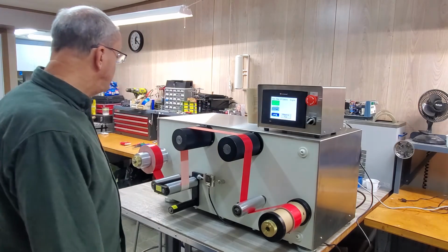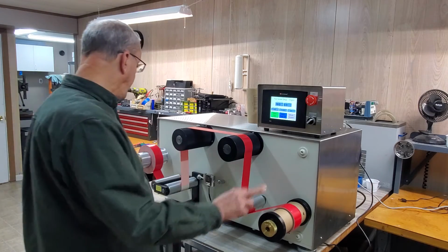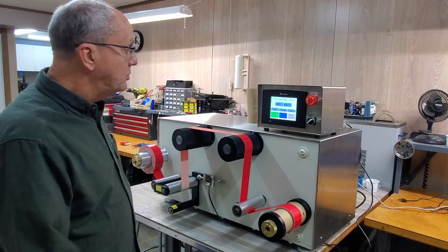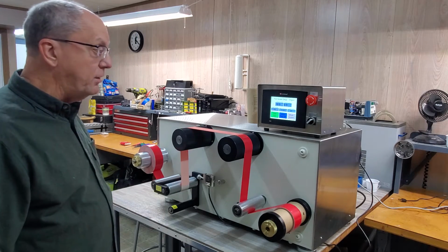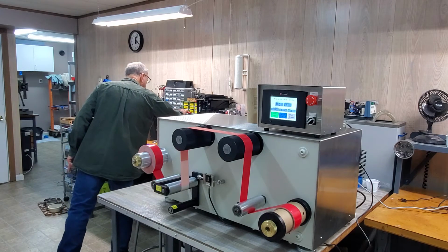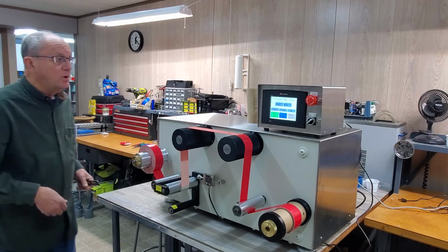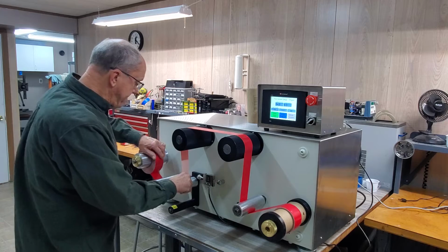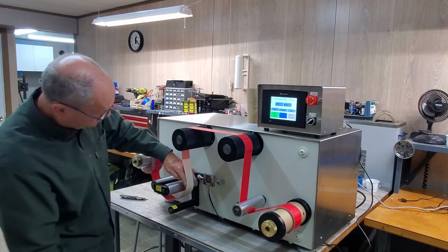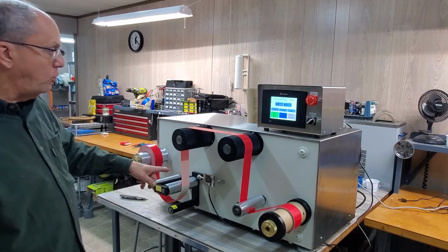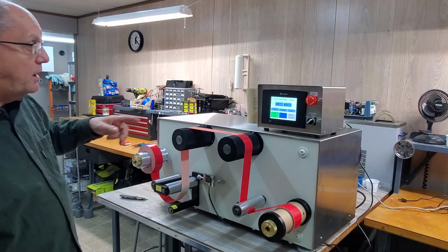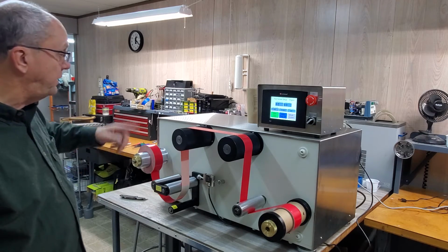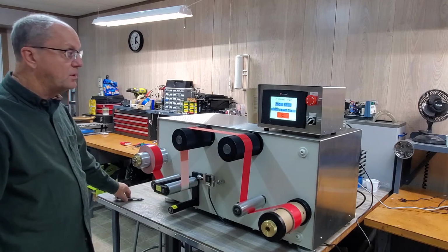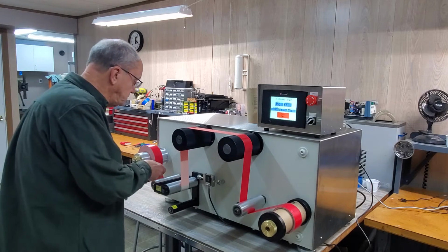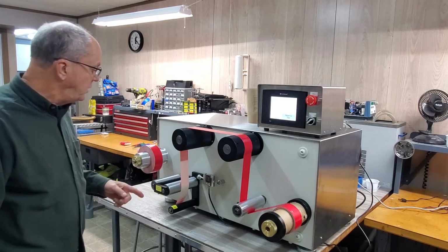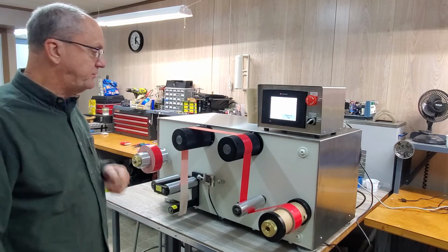Obviously, all this stuff can be changed at any time. So what I'm going to do is run a test, and I'm somehow going to make this thing go slack so that I can demonstrate how this auto shutoff works. So here we go. First of all, let's put some slack in the web. So you can see I have no tension on here at all at this point. So we have 1 foot for this thing to catch up, and then the automatic inhibit and the automatic shut off will kick in. So here we go. You can see when I cut the web, our tension went to 0 and the test ended.